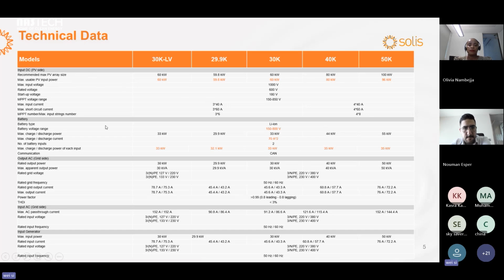For the PV side, the DC side, we can do a 2 times DC-AC ratio. So for example, if you have a 30k inverter, you can configure 60 kilowatts of PV panels for your plant.